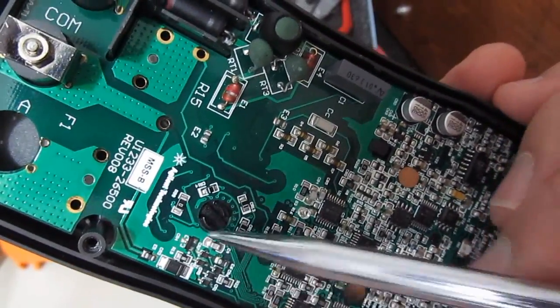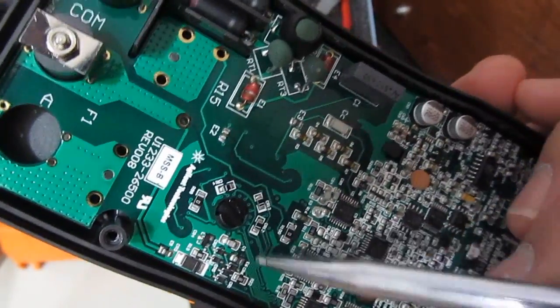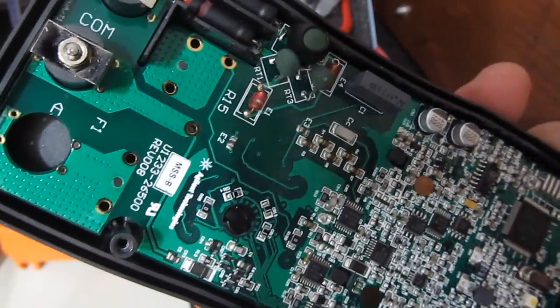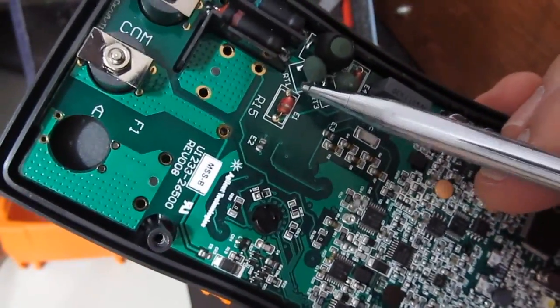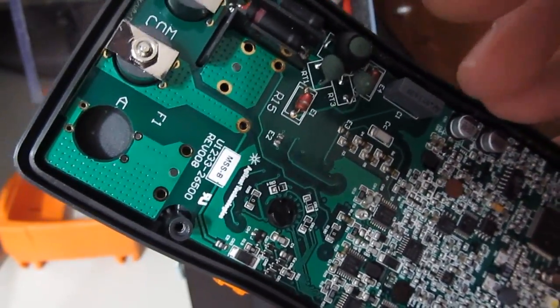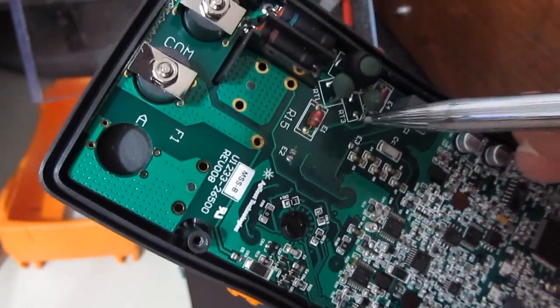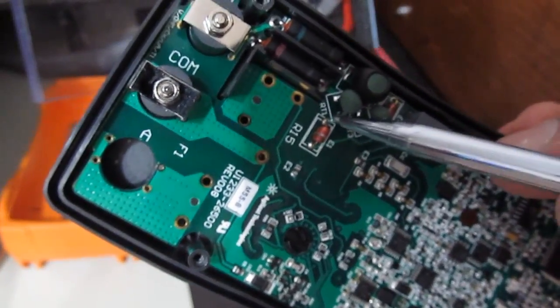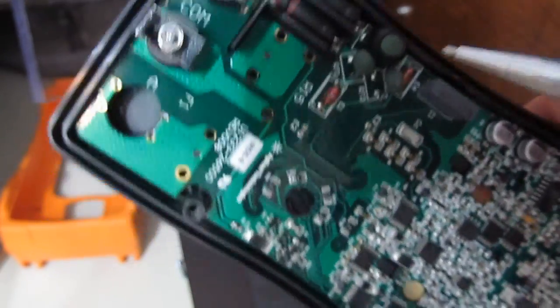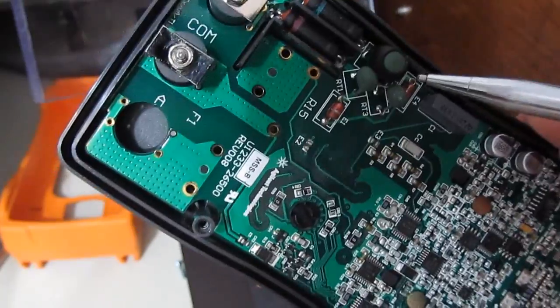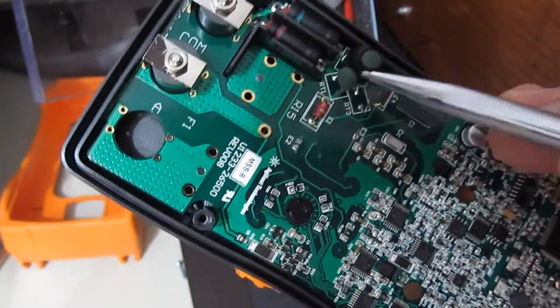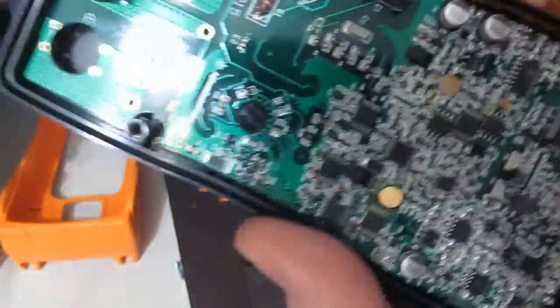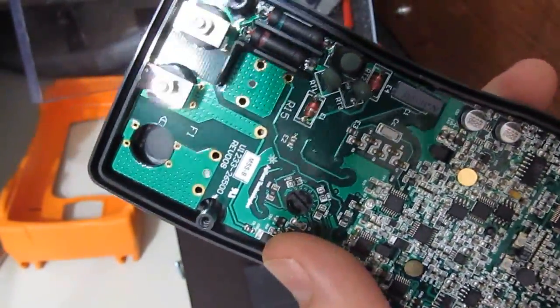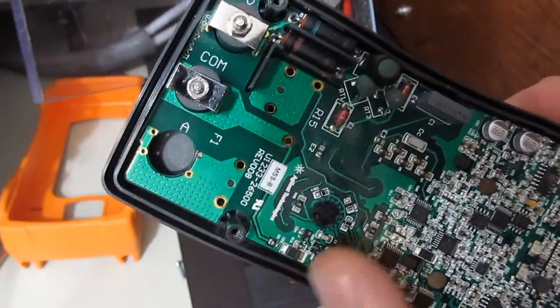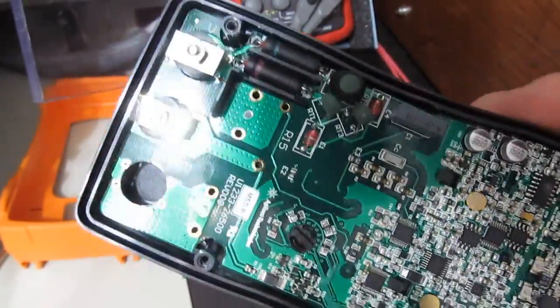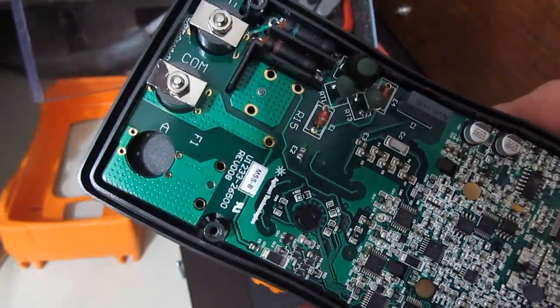And when you select the ohms mode, it basically enables these diodes, which clamps the voltage at these two locations. And you'll end up getting about maybe 5 volts here. So the entire voltage drop is across these two resistors in the PTC. And it basically holds the side of the gas discharge tubes, not at ground, but a few volts above ground. So all that power gets dissipated by these two devices. So there is some downstream protection for ohms mode. Again, these are not in play when it's in voltage mode. So again, I think it's just going to be interesting when I finally do test this thing on the transient generator.